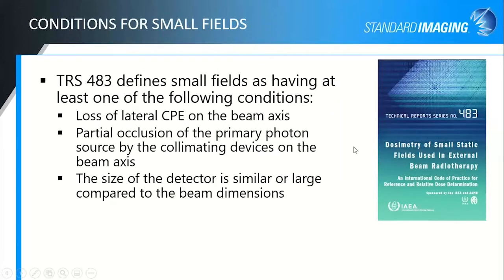So, conditions for small fields. What makes a small field? TRS 483 defines small fields as meeting at least one of these three conditions. Number one, loss of lateral charged particle equilibrium on the beam axis. Number two, partial occlusion of the primary photon source by the collimating devices on the beam axis. And number three, the size of the detector is comparable to, similar to, or large compared to the beam dimensions. If you have any one of these conditions, then you are measuring small fields, or you are in that area of small field dosimetry, and so you need to make consideration for a lot of these various factors that affect your measurement when you have these conditions.